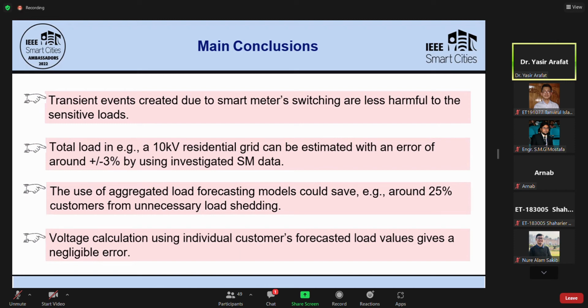In the present scenario, when we disconnect load from the medium voltage substation, no other customers are connected. But with selective load shedding, there will still be some customers connected, and it is important to provide them with good voltage quality. So that's why voltage calculation is important. By using this load flow analysis, we can easily calculate voltage for the remaining customers so that we can take necessary steps when needed.